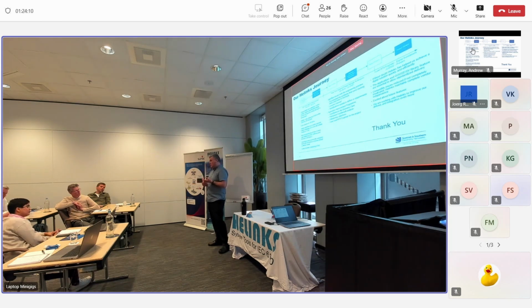Things like PTP, SNTP, syslogs, the ports that you need open to allow vendor tools to communicate with the IEDs to configure them, and ports open for things like Triangle Microworks and Station Scout so you can do diagnostics. Anything not in the SCD file is catered for in the Visio file, which forms the full flow controller configuration.